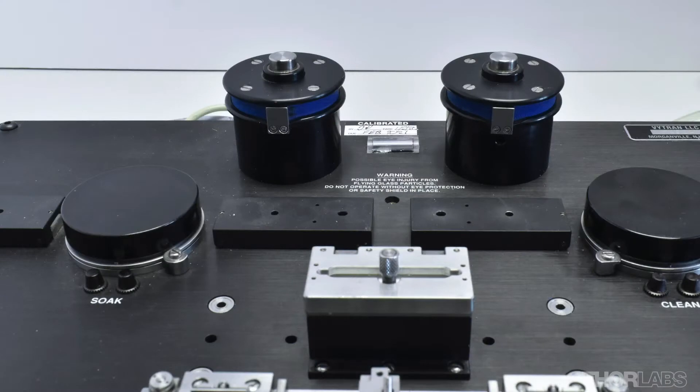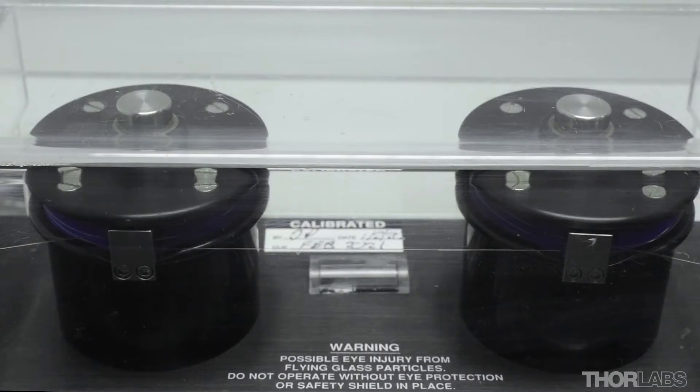Some models of the FFS2000 workstation are fitted with a rotary proof tester. This video will discuss how to use the proof tester to determine either the breaking strength of a splice or if the splice meets a minimum strength requirement.